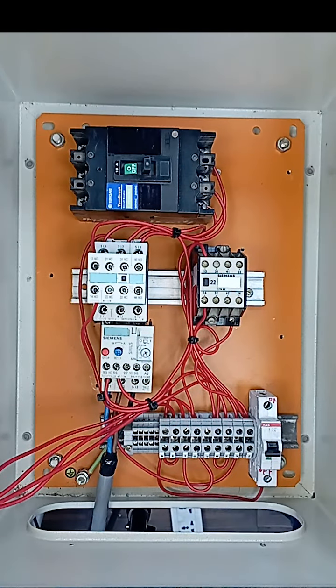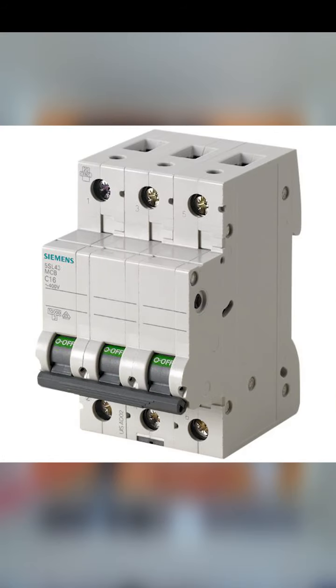This is the direct online starter circuit. It consists of three main components: the MCCB or circuit breaker, the contactor and thermal overload relay for overload protection of the equipment. A circuit breaker is an electrical safety device that is designed to protect an electrical circuit from damage caused by an overcurrent or short circuit. Its basic function is to interrupt current flow to protect the equipment and to prevent the risk of fires.